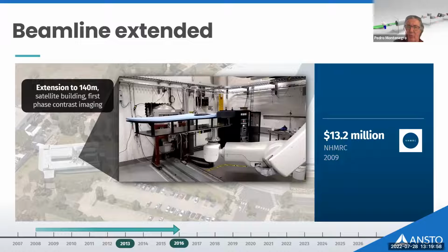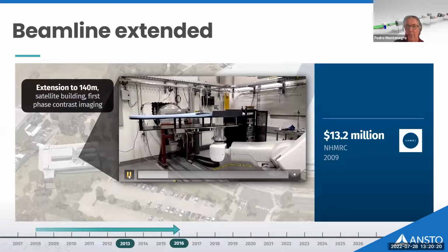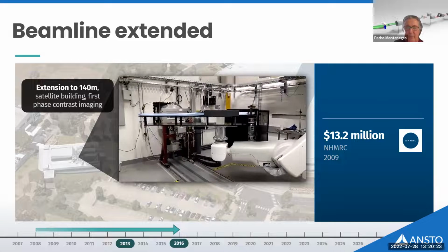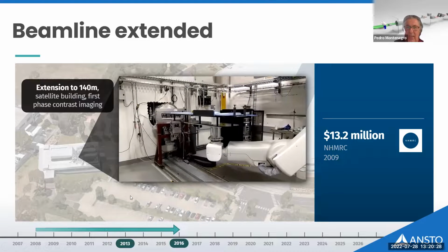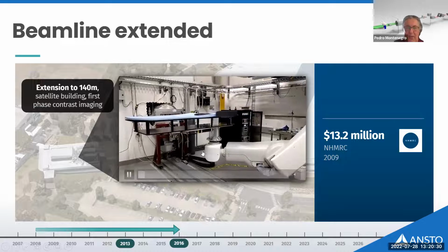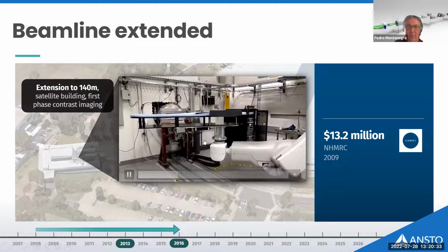You can see the bed sitting on the robot, but this $1.5 million robot to position the patient and to do the CT scan using the rotation stage on the robot was added, if I remember right, in the early period of 2016. And that, I think, let's see if it runs. Yes, you can see a rotation about the breast position of the bed. We have tested rotation up to 30 degrees per second, and that is what we are at the moment.